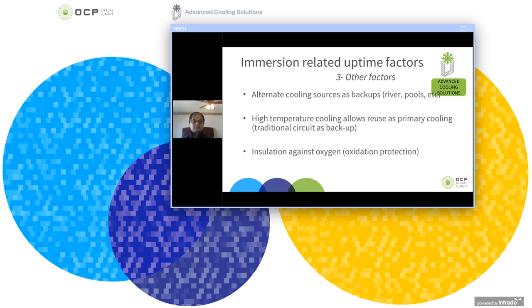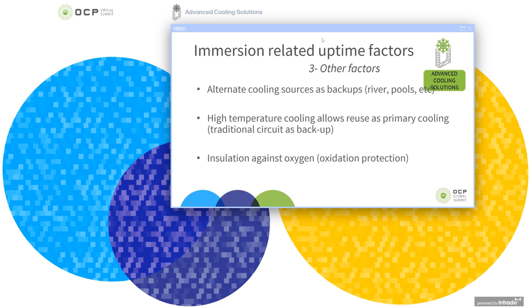And one of the things that I'm known for making a point of, and it's part of a passion of mine as well, is that if you optimize for high temperature cooling, what you're actually generating is high value, high grade heat, which makes it much more attractive to consider reuse scenarios, because high grade heat is valuable. It's worth money in most areas in the world. Putting that into a reuse scenario effectively means that the reuser becomes your cooling circuit.